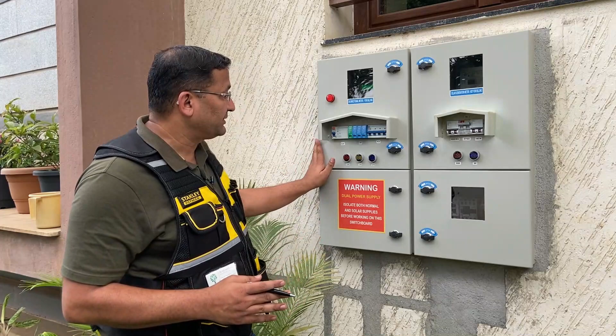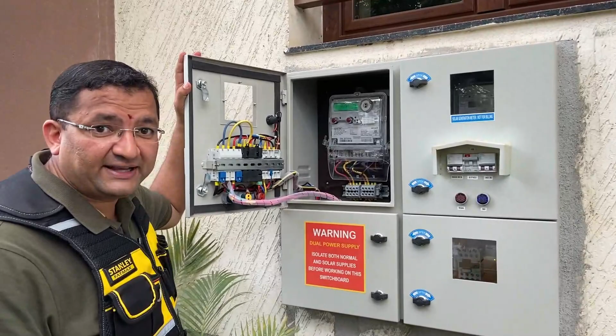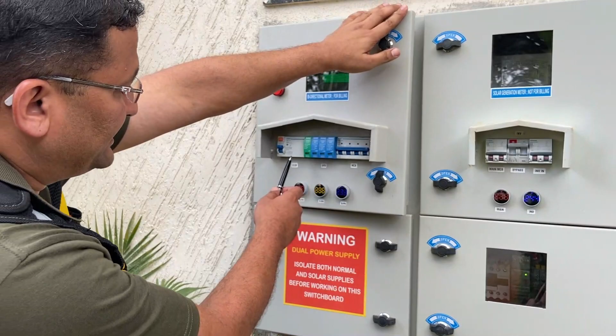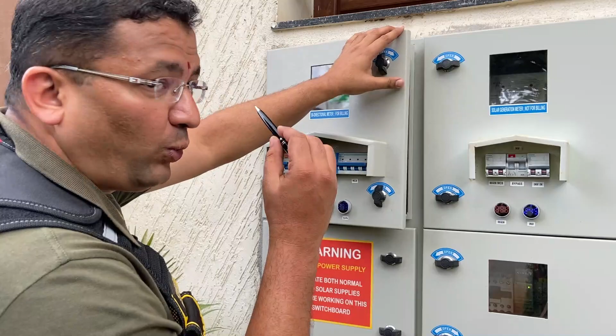So the wiring on the AC side of the inverter starts from here. This is our main incoming line. Since it's a 3-phase incoming line, this is our 3-phase meter. The meter output is connected to an ELCB, a 1+2 SPD, and an MCB. After this MCB, the load goes into the house.